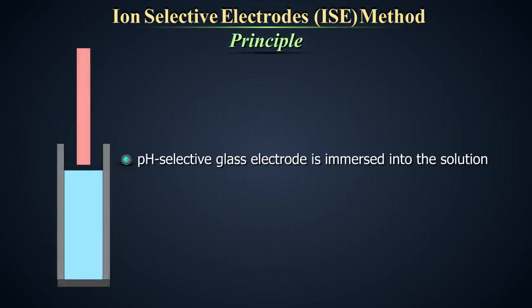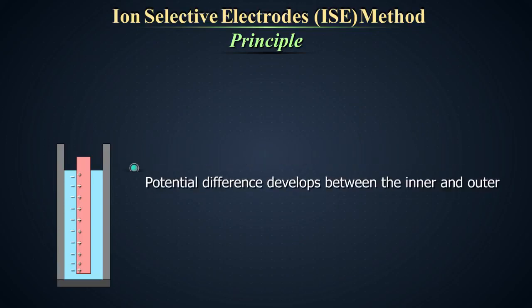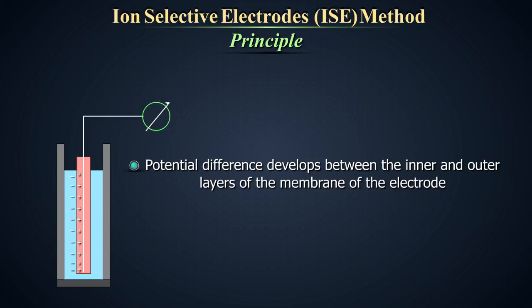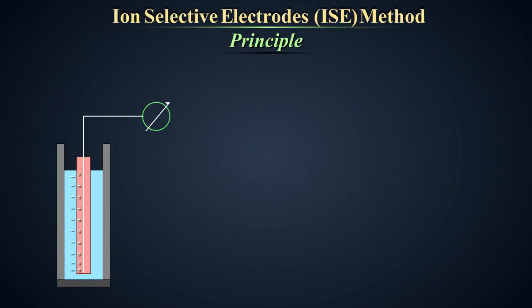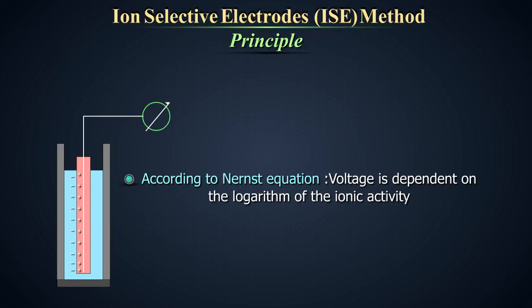A pH-selective glass electrode is immersed into the solution whose ion concentration is to be measured. When the ion-selective electrode is immersed into the solution, a potential difference develops between the inner and outer layers of the membrane of the electrode, which is related to the ionic concentrations of the solution. The voltage is theoretically dependent on the logarithm of ionic activity according to the Nernst equation.